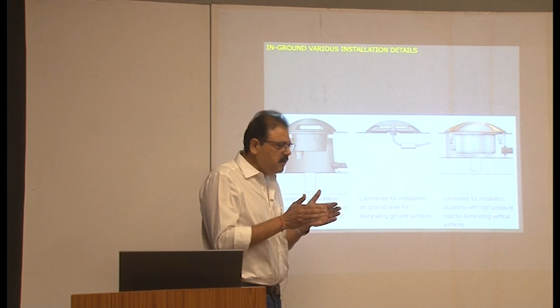This is some kind of connector, where two wires get connected with an IP connector. When we use an IP connector, the electrical connection must be equal to or greater than the IP rating of the luminaire. If you use a connector whose IP rating is the same or lesser than the luminaire rating, even this will fail. So this has to be higher than the IP rating of the luminaire.